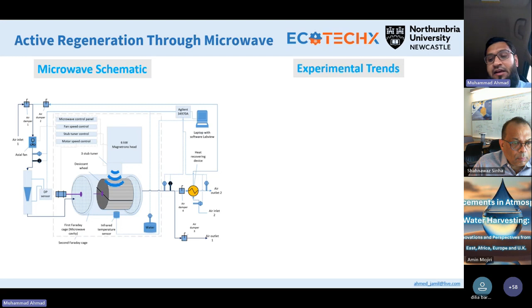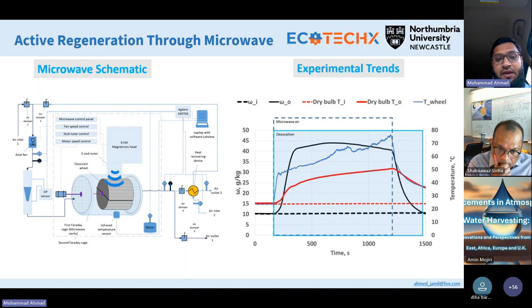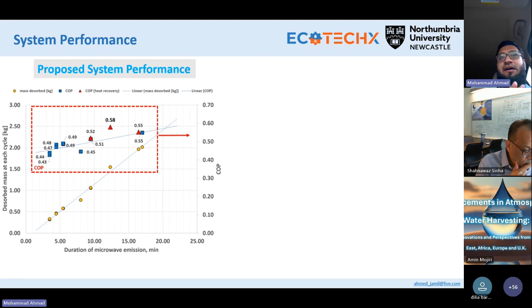When we tested this microwave based regeneration arrangement, we can see that this dotted line shows the omega inlet of the air that we were taking from outside, and the omega outlet is showing close to 45 gram per kilogram from directly 10 gram per kilogram, which shows high regeneration efficiency for this heat exchanger based silica gel arrangement that we were using in the system. Then we evaluated the COP of our system at different durations of microwave emissions, and we were able to achieve around 0.58 COP, which is slightly higher than conventional arrangements, where they normally report close to 0.25 or 0.3.